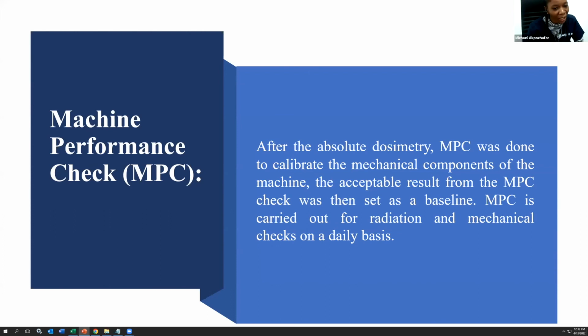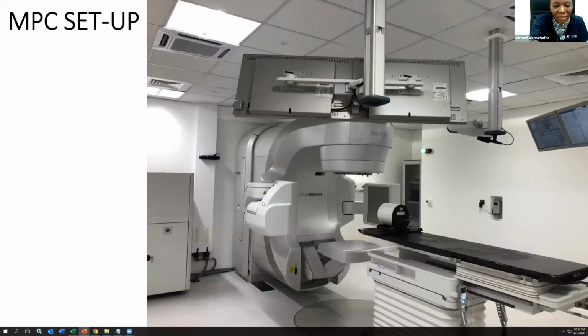Because we use a Varian system, the TrueBeam LINAC is manufactured by Varian Medical Systems, Varian has a tool called the machine performance check. It is not that we use this to replace QA, but it is a kind of test carried out to keep assuring the quality of your machine. After dosimetry is carried out, we do MPC. In this MPC we do mechanical tests, and we also carry out dosimetric tests. And this is done daily.